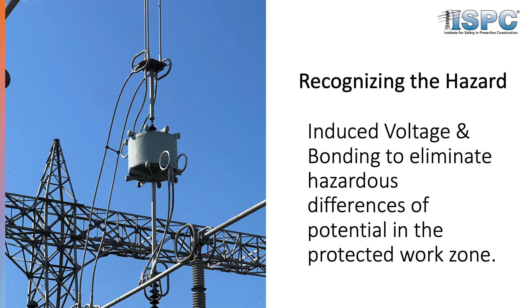And the very last thing, or the next to last thing they did, was remove the cable to paddle flat connection at the bottom of the wave trap from the second lead, the last lead that was remaining. Well, as you can imagine, right now that's their ground path. Their grounds - they have put up no temporary safety grounds to bypass around this open point they're about to make in this circuit. They have in their mind the whole time, I'm grounded, I'm good.